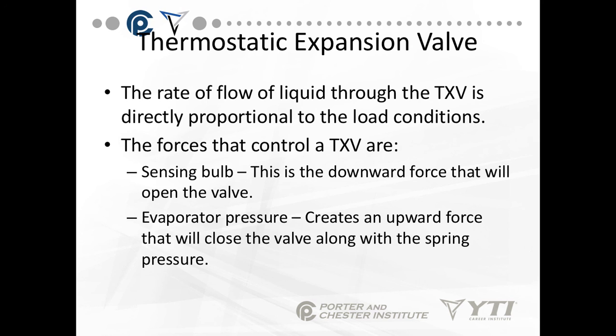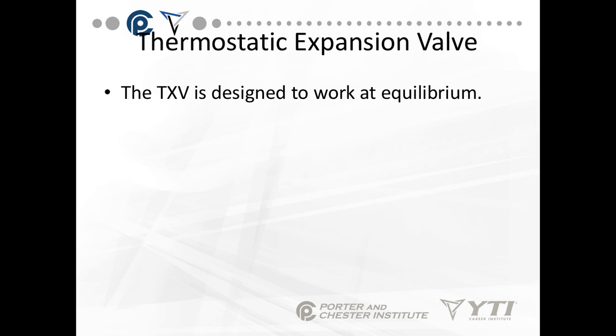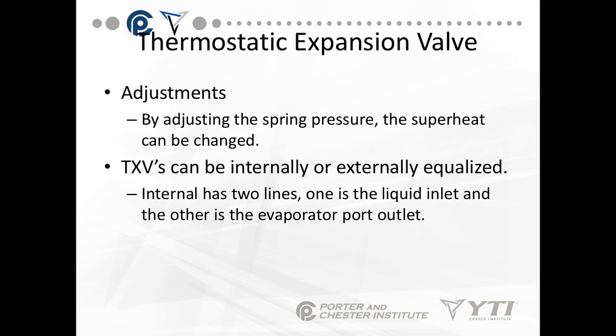The rate of flow of liquid through the TXV is directly proportional to the load conditions. The forces that control the TXV are: the sensing bulb gas that expands and contracts — a downward force that opens the valve — and the evaporator pressure, which creates an upward force that closes the valve along with the spring pressure. The TXV is designed to work at equilibrium. By adjusting spring pressure, the superheat can be changed. TXVs can be internally or externally equalized.